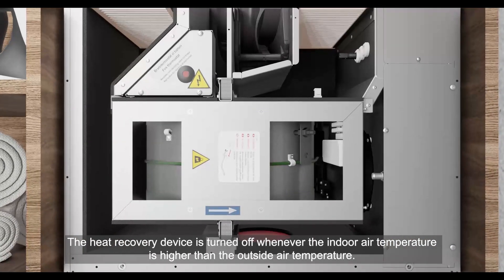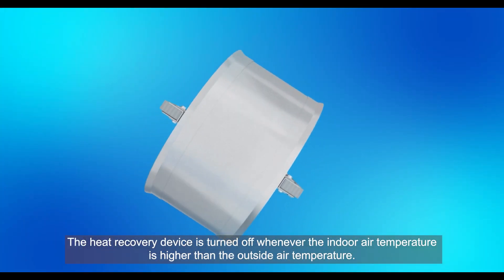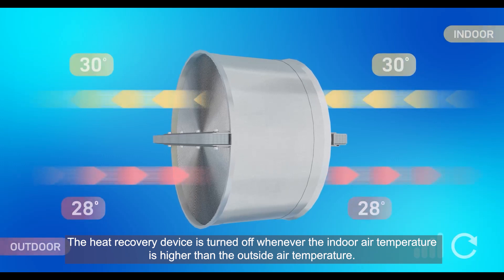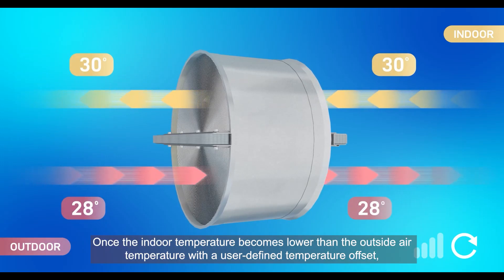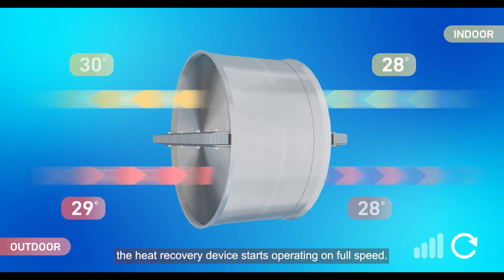The heat recovery device is turned off whenever the indoor air temperature is higher than the outside air temperature. Once the indoor temperature becomes lower than the outside air temperature with a user-defined temperature offset, the heat recovery device starts operating on full speed.